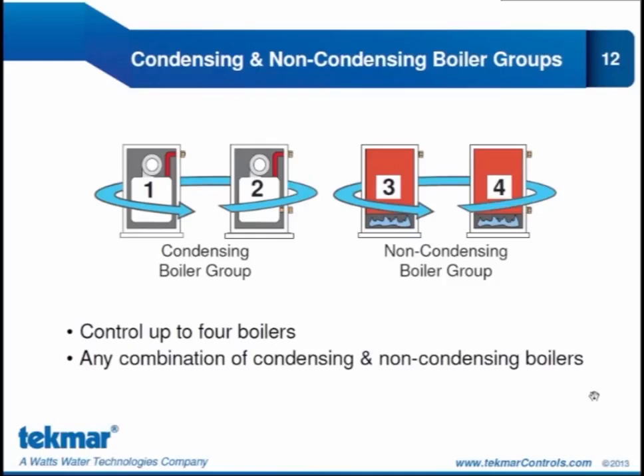If there is more than one condensing boiler being configured, the 284 will automatically create a condensing boiler group. Likewise, if there is more than one non-condensing boiler being configured, the 284 creates a non-condensing boiler group. Rotation happens separately within each of these groups, which makes sense because it's very likely that each of these groups will have different run times.